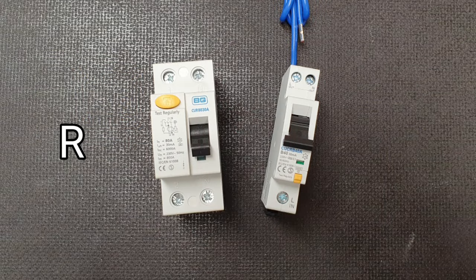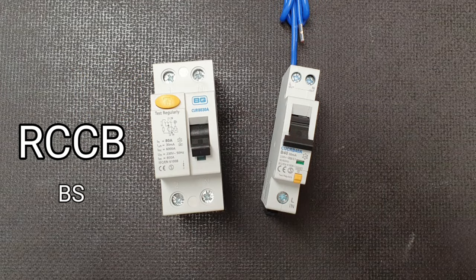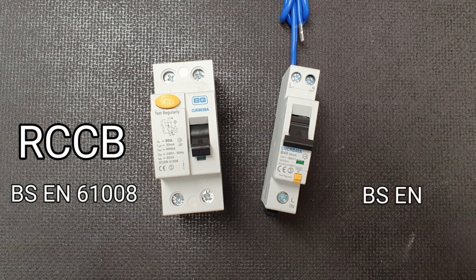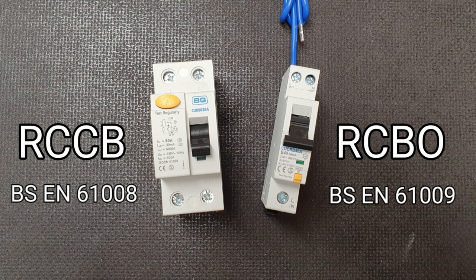And that is essentially what an RCCB manufactured to meet the requirements of BS EN 61008 is doing. It has no facility to detect an overcurrent from a short circuit or an overloaded circuit. However, if we add 1 to our BS EN number, we get BS EN 61009, and that is the standard that an RCBO is manufactured to. Do you remember what the O stands for? Overcurrent. So this clever little device monitors for earth faults, as we outlined earlier, but it also contains the components for detecting an overload caused by connecting too many loads to a circuit, and also when large currents flow due to a short circuit.